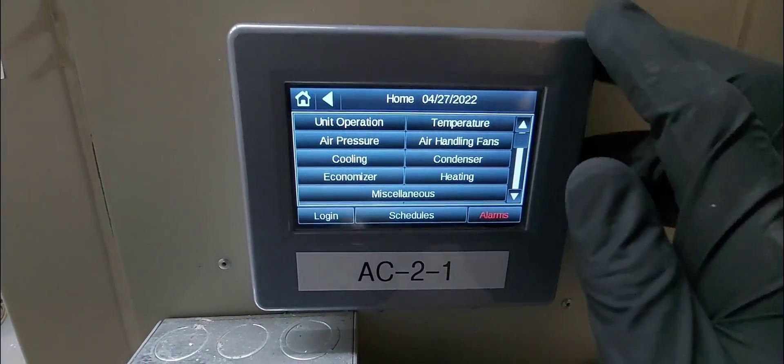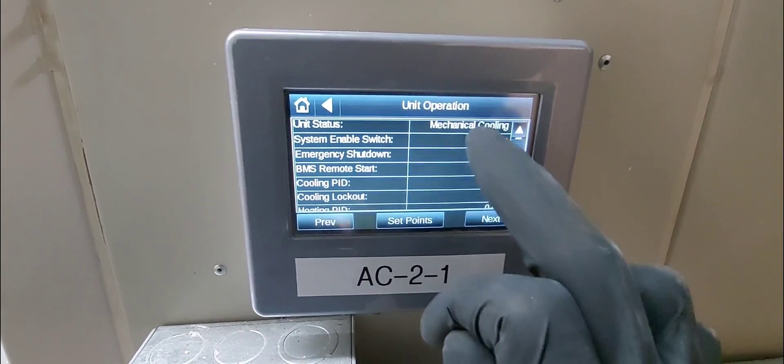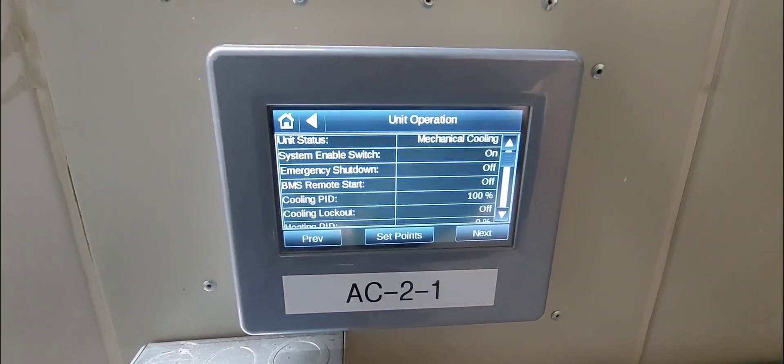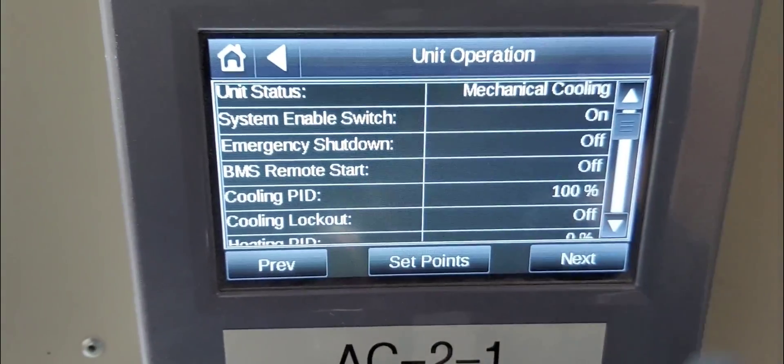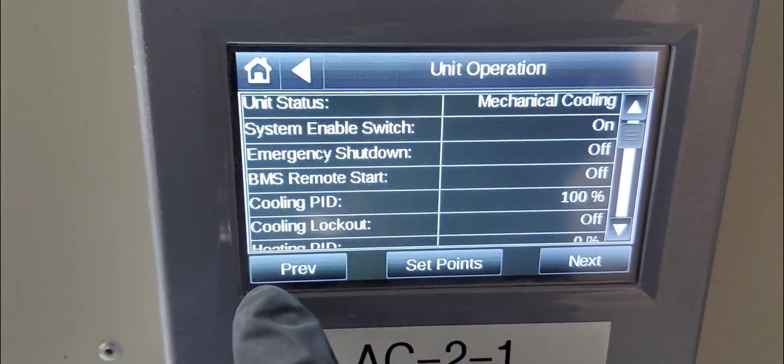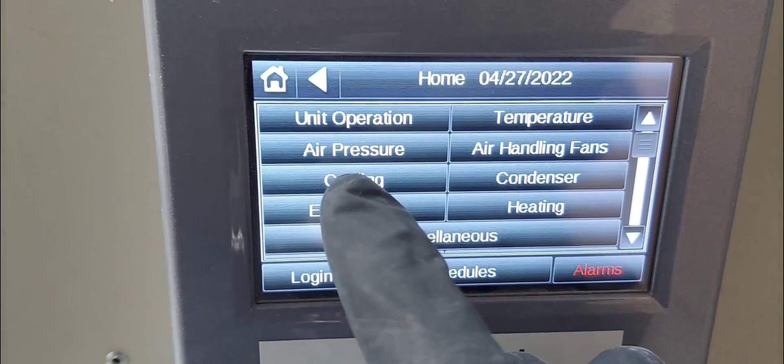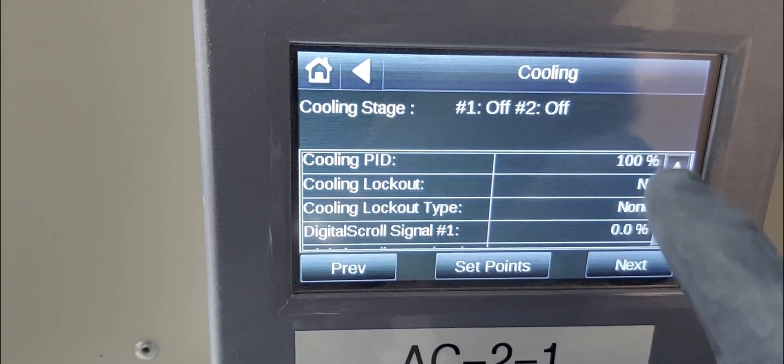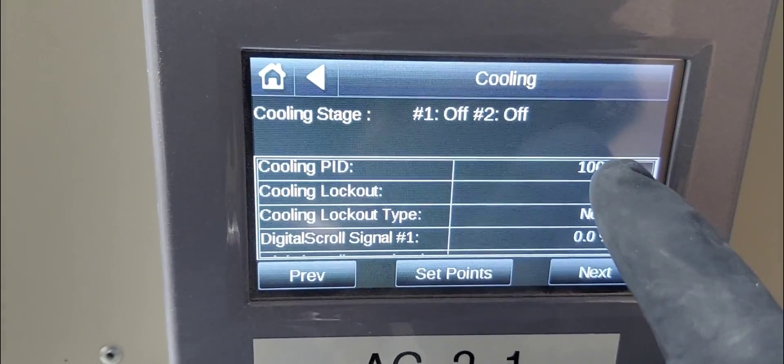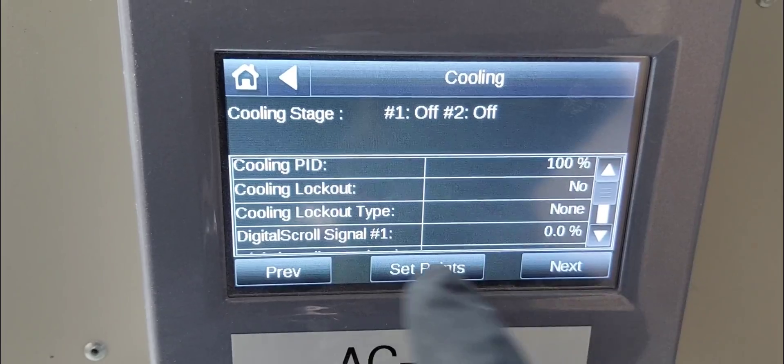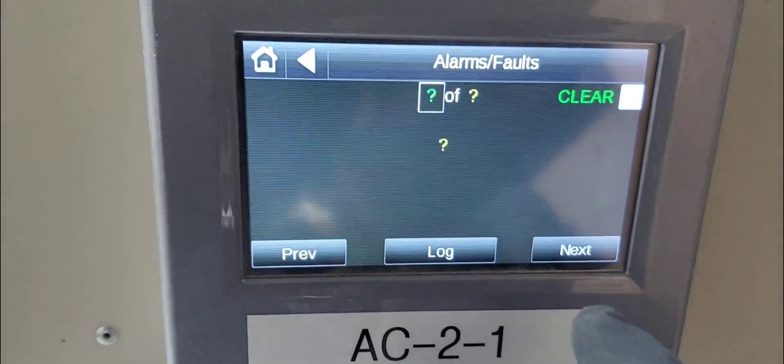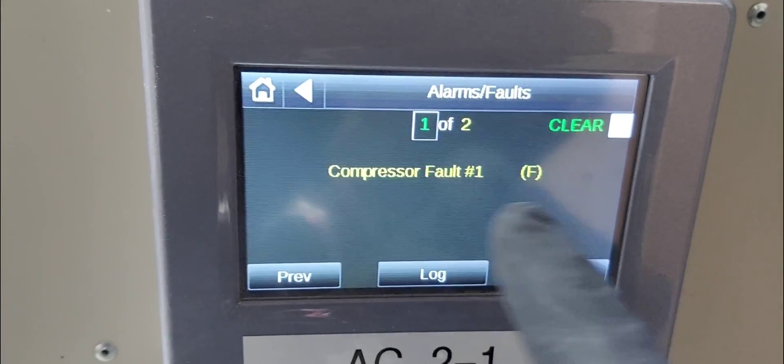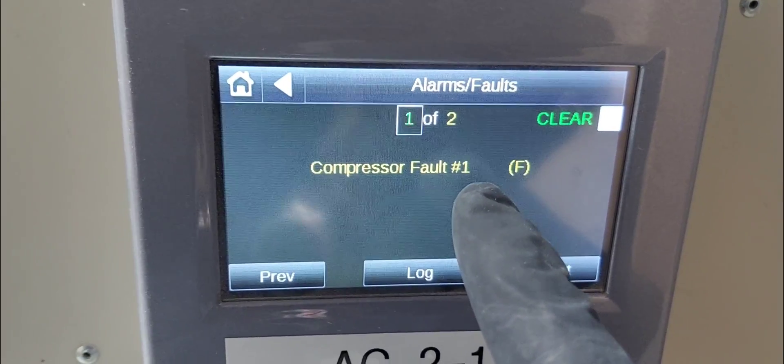Here we are. Unit operation - it's in mechanical cooling. You can see. If I go back into faults, we're calling for cooling 100 percent. See right there. And we go back to home alarm - compressor fault number one.